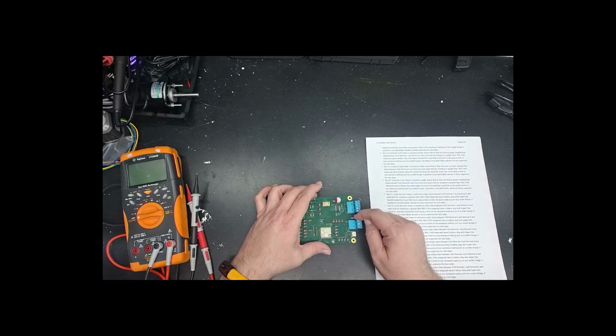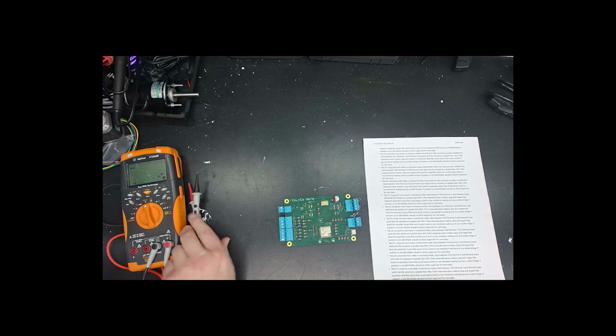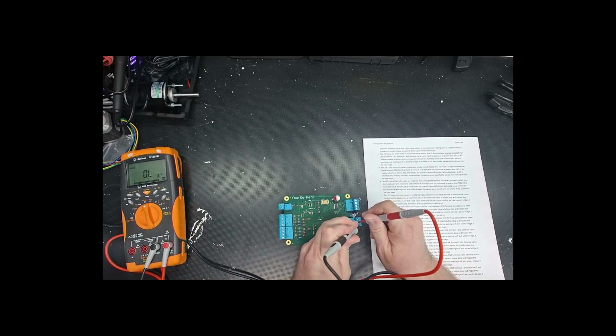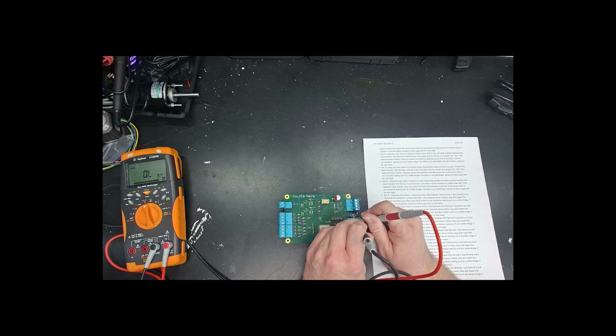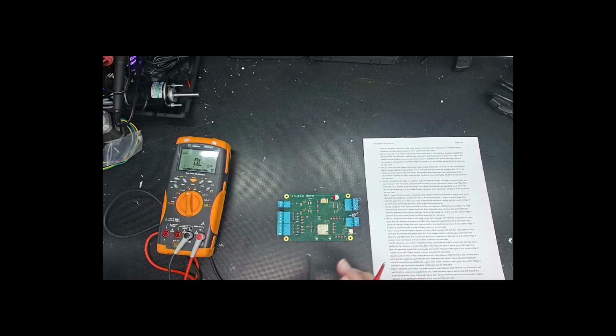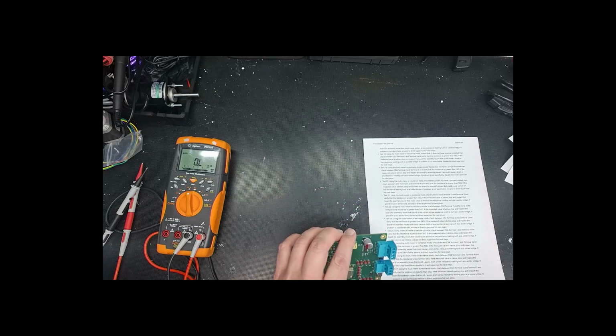So schematically, with that jumper enabled, A and B should have 120 ohms resistance. Not an overload, which is wrong. That should not be, because schematically, let's pull up my printout. Schematically, unless I'm, oh, you know what? Don't tell me I got those. No, one. Oh, pin one. 1 and 2. Now there could be a layout issue.